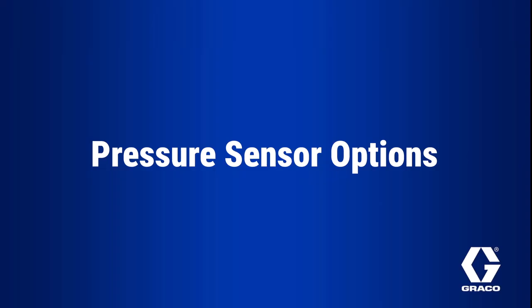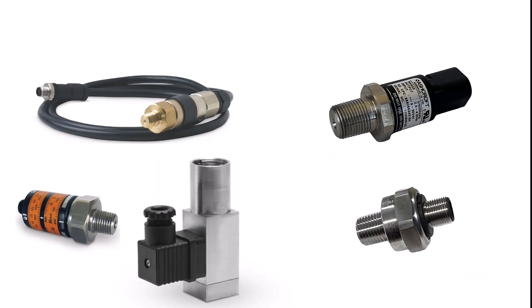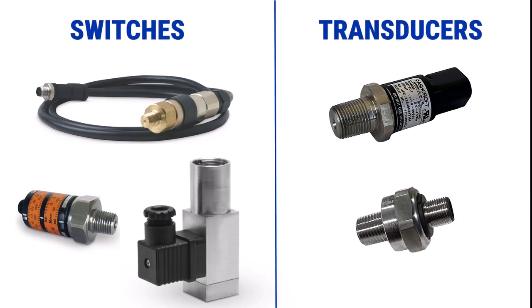Before I go, let's look at some different models of pressure sensors. Pressure sensors can be broken into two main groups, switches and transducers. A pressure switch simply opens and closes the circuit connected to the P input. It closes when the pressure is at or above its setting, and it opens when the pressure is lower than its setting. The G3 Max uses this open or closed state to determine the status of the injector system. Here are a few forms of pressure switches that Graco sells for the G3 Max.